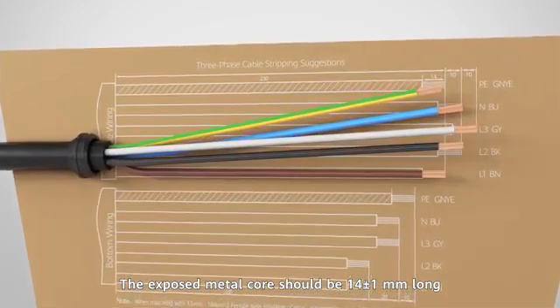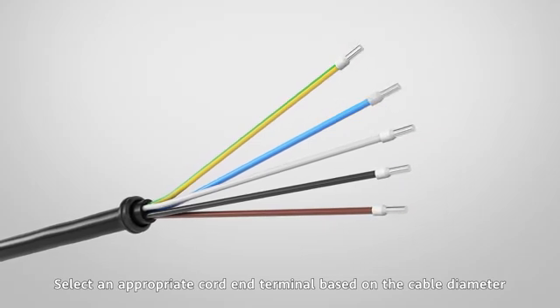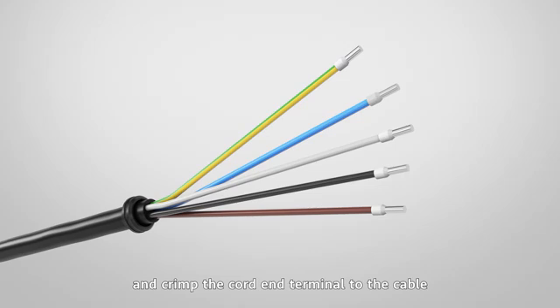Strip the cable to the recommended length. The exposed metal core should be 14 plus or minus 1 millimeters long. Select an appropriate cord end terminal based on the cable diameter, and crimp the cord end terminal to the cable.